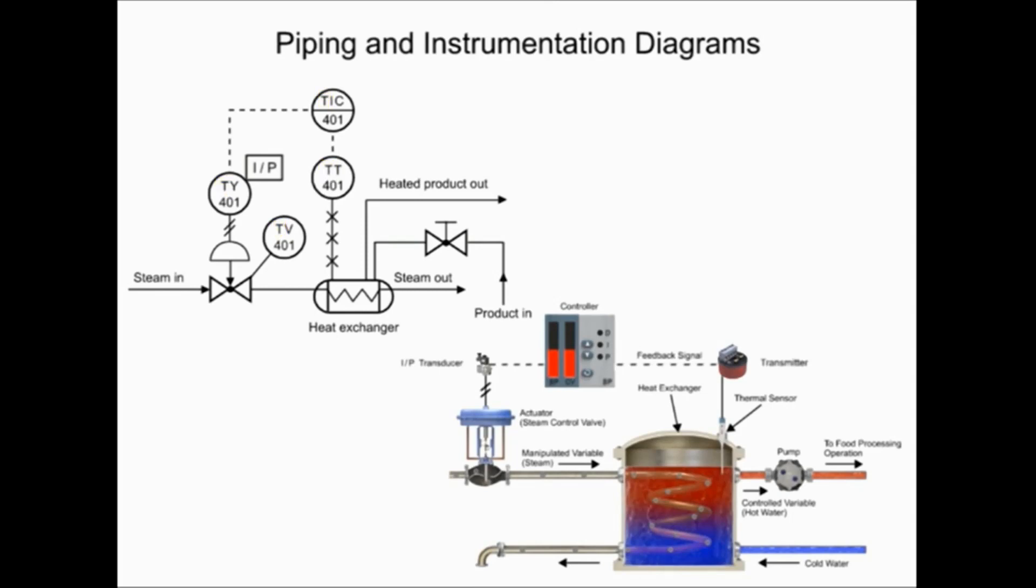The instrument connected to the heat exchanger contains two other types of information. The second letter in the functional identifier indicates it is a transmitter, and the balloon with no line inside its symbol indicates the device is field mounted.